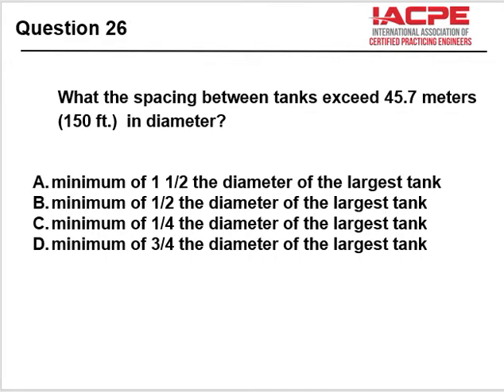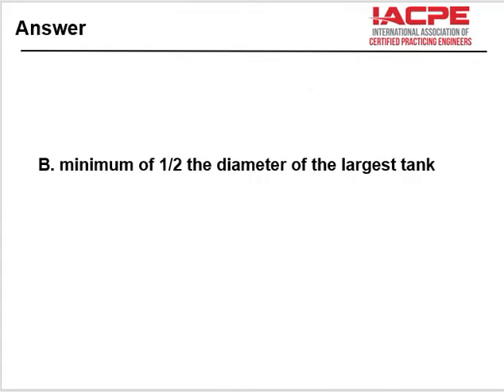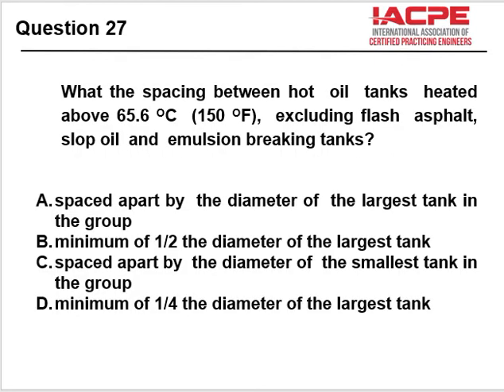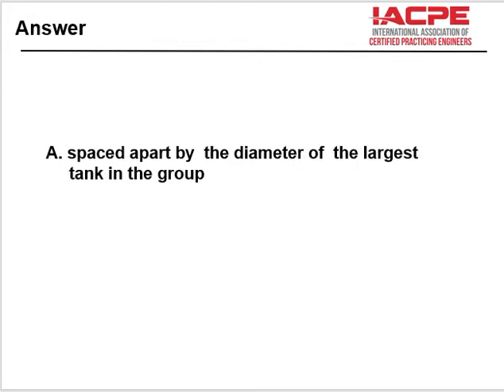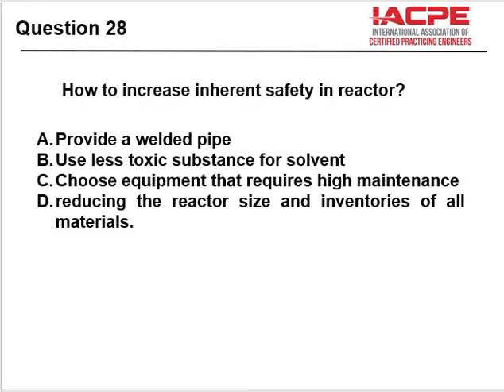What is the spacing between tanks exceeding 45.7 meters, 150 feet, in diameter? It's a minimum of 1/2 the diameter of the largest tank. What spacing between hot oil tanks heated above 150 F, excluding flash, asphalt, slop oil, and emulsion breaking tanks? Spaced apart by the diameter of the largest tank in the group. And this is safety and spacing.